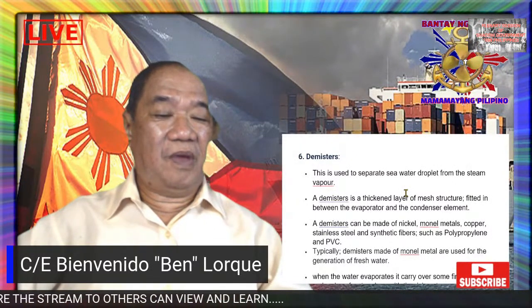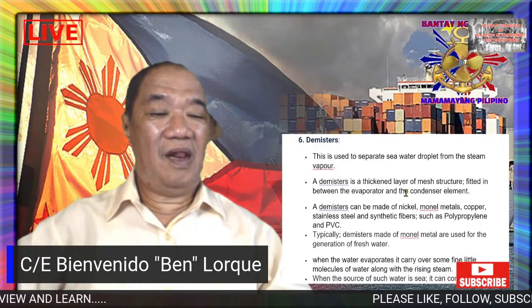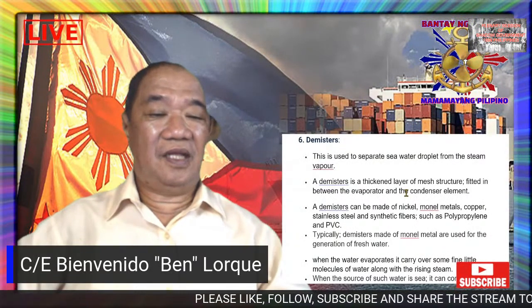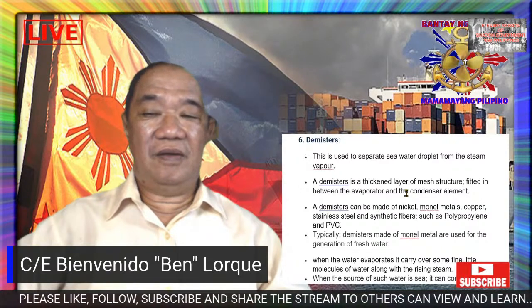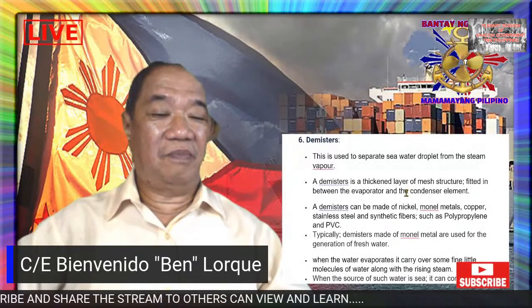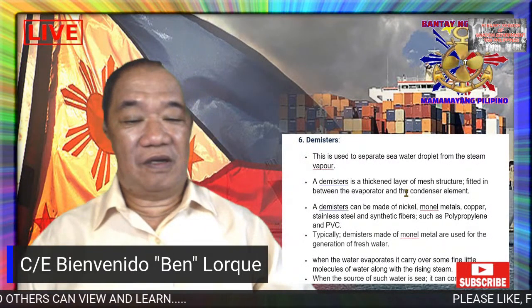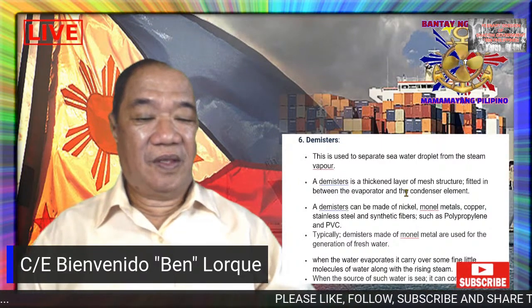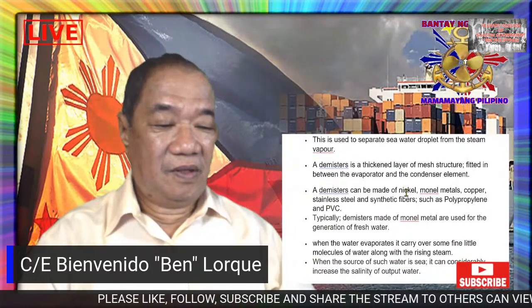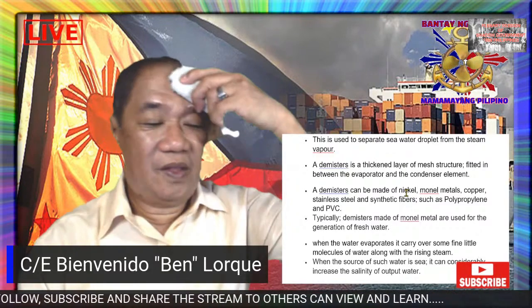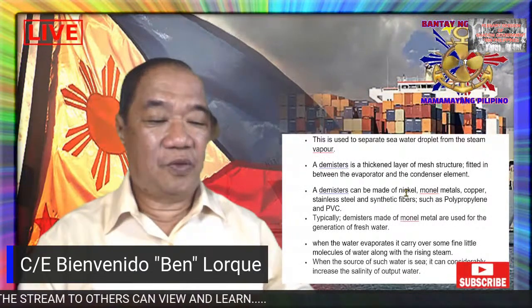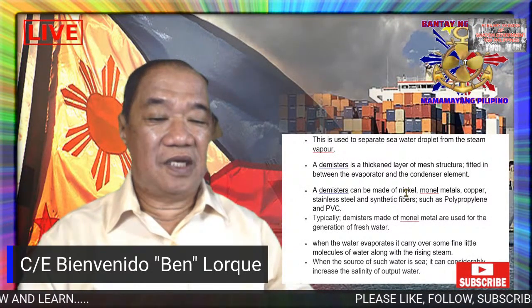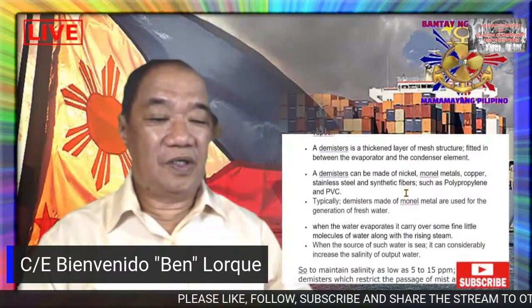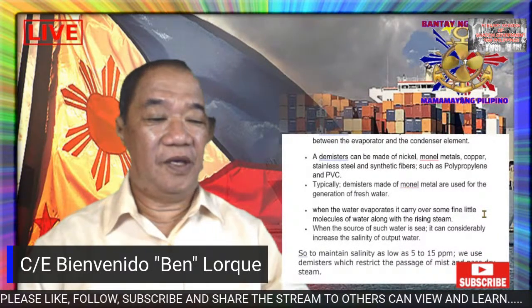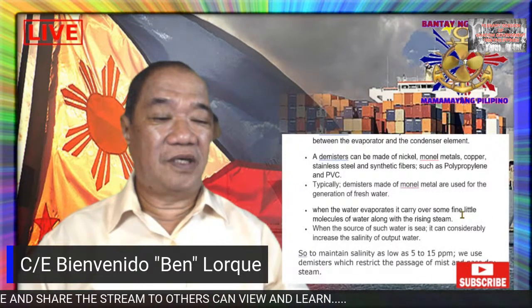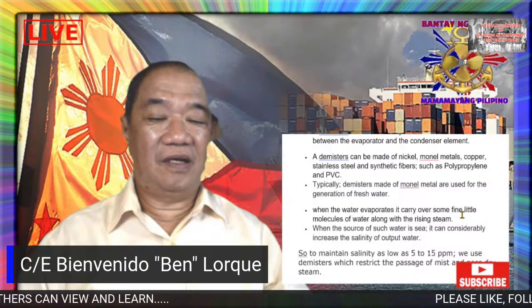And the demister can be made of nickel, monel metal, copper, stainless steel, and synthetic fibers such as polypropylene and PVC. Typically, demister made of monel metal are used for the generation of fresh water. Now, when the water evaporates, it carries over some fine little molecules of water along with the rising steam. When the source of such water is sea, it can considerably increase the salinity of output water. So to maintain the salinity as low as 5 to 15 ppm, we use demister which restricts the passage of mist and passes dry steam.